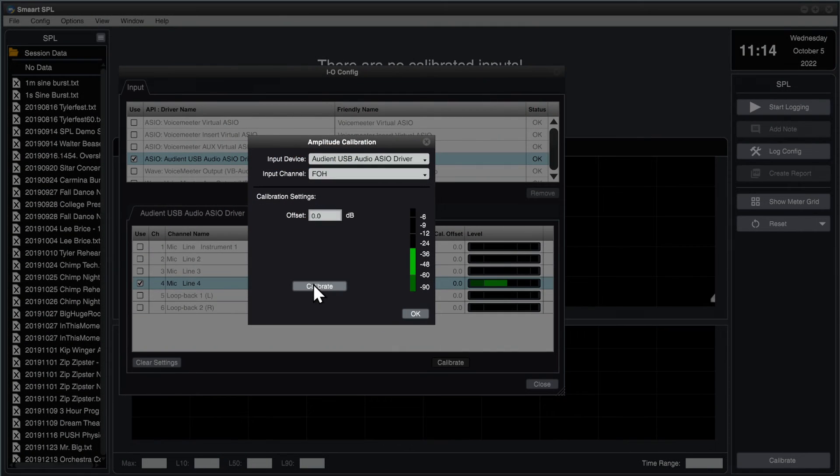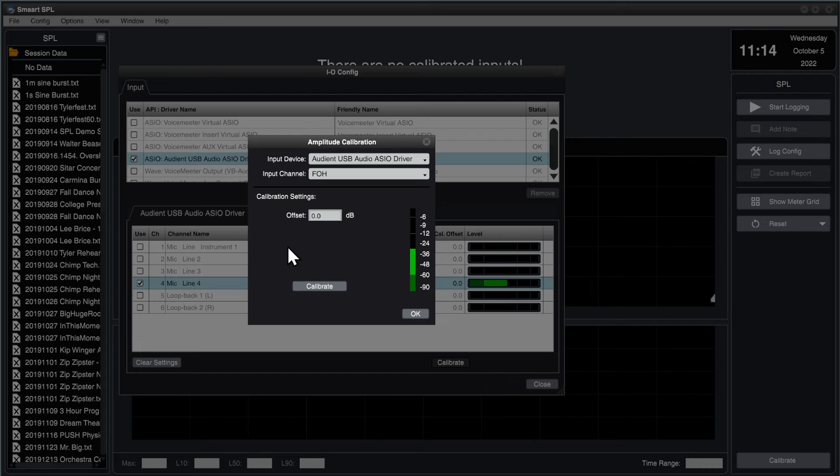Now that my gain is set, I'm going to click the Calibrate button. Be sure to keep the microphone quiet and still while the calibration process runs.